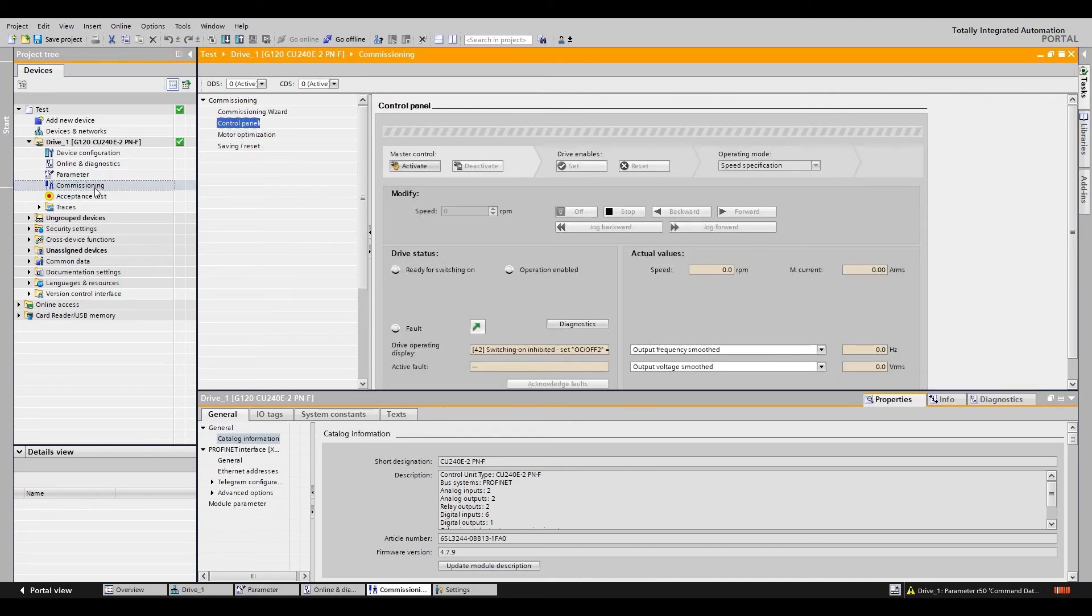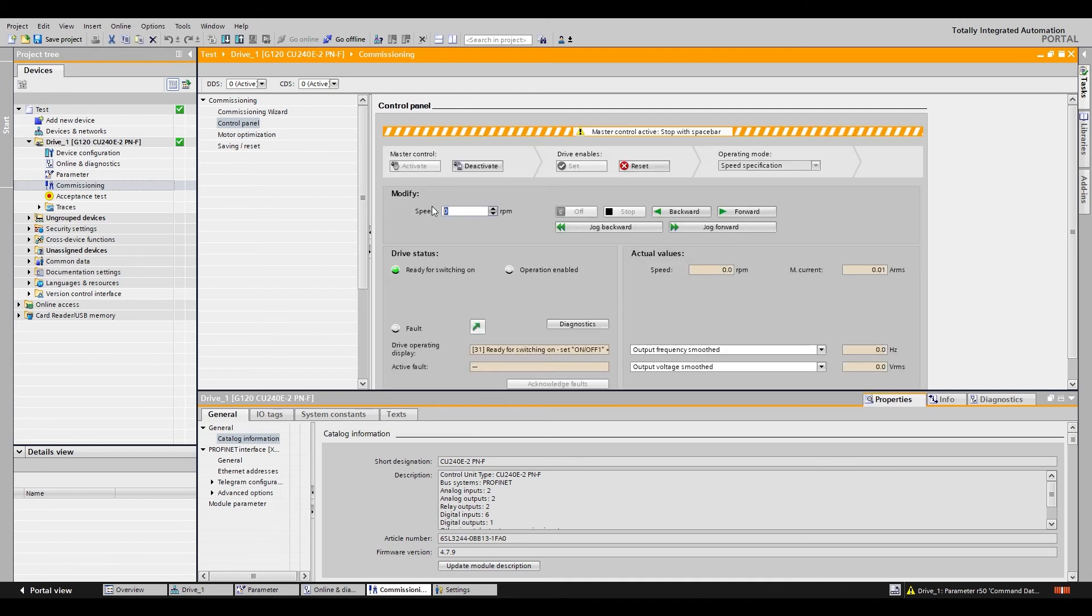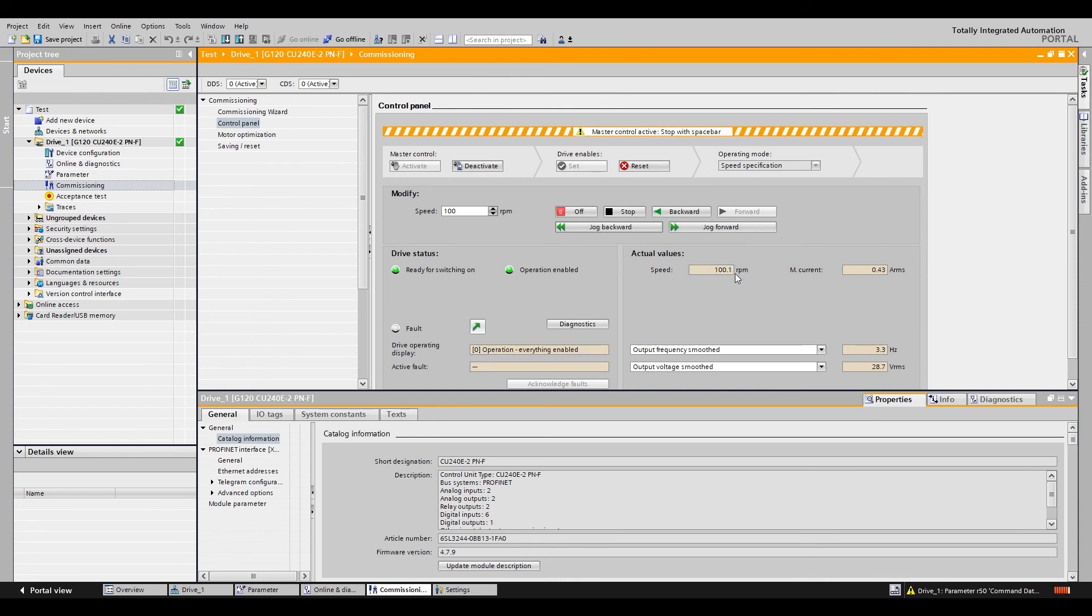Now we will go to the control panel. Activate master control. Hit accept. Give the drive a speed. We'll do 100 rpm. I'll set it to go forward. You can see that it's operating everything's enabled and the speed is roughly 100 rpm.